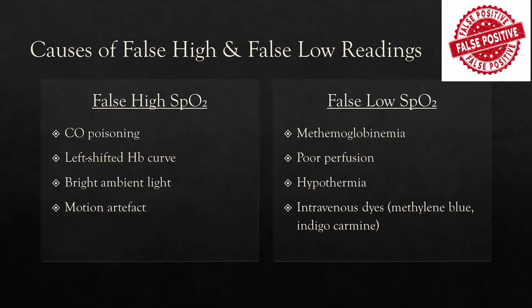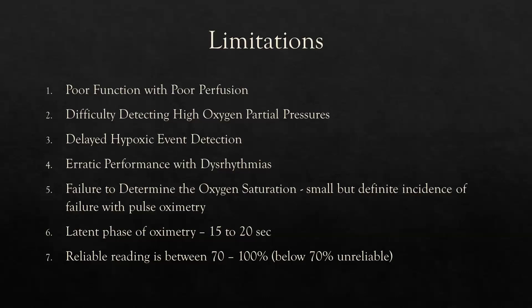And limitations of pulse oximeter. Poor function with poor perfusion, difficulty detecting high oxygen partial pressures, delayed hypoxic event detection, erratic performance with dysrhythmias, failure to determine the oxygen saturation, small but definite incidence of failure with pulse oximetry, latent phase of oximetry, which is for a duration of 15 to 20 seconds. Reliable reading is between 70 to 100%.